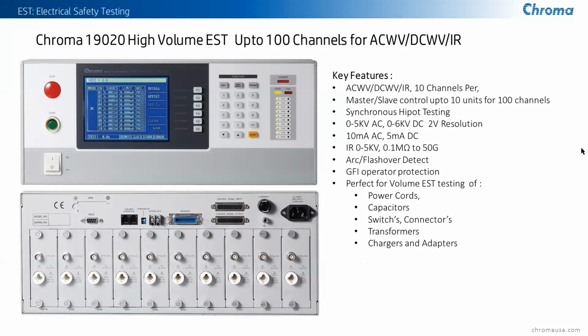If you have a higher volume requirement, Chroma offers the 19020 high volume EST testers. This one gives you up to 10 channels, with each of these being able to be grouped together for up to 100 channels total. It also has a feature known as synchronous hipot testing, and what this does is give you the ability to ensure that when you have multiple channels side by side, the voltages are synchronized so that they will not produce a high differential voltage between the channels. By having the voltages synchronized, they will always have a 0 volt differential proportionally between the two channels to prevent excessive high voltage.